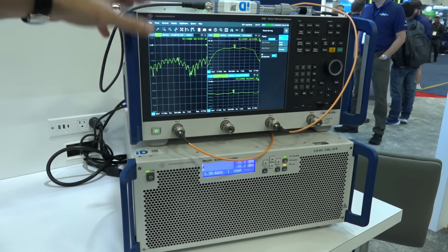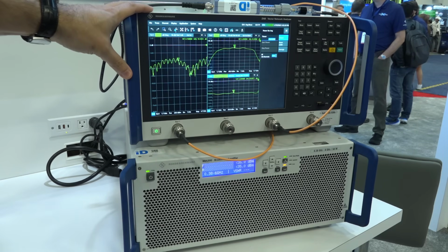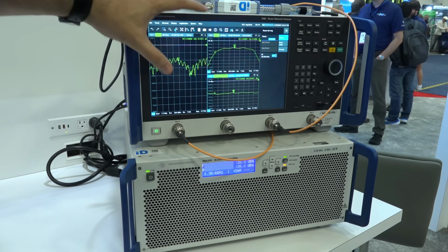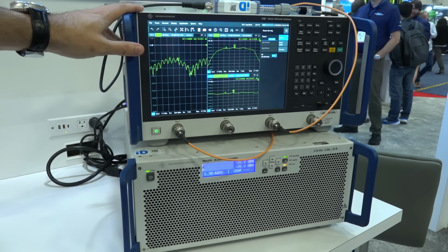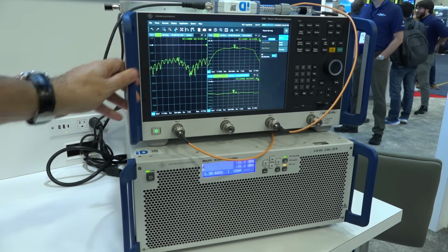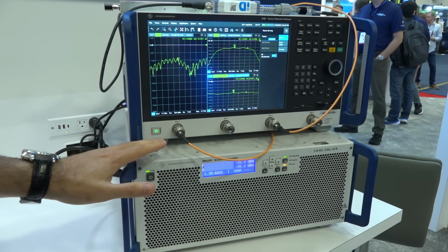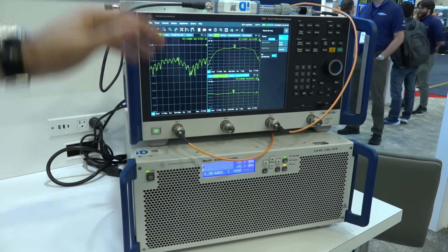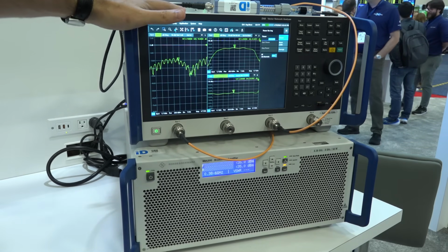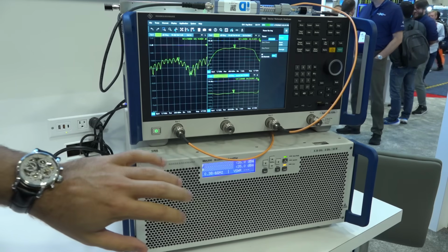The ZNB is essentially a production line kind of instrument where you can run a lot of rapid measurements. It has compression gain measurements and everything on top of it. Now the setup here is interesting because Rohde & Schwarz have their own very high power amplifiers.